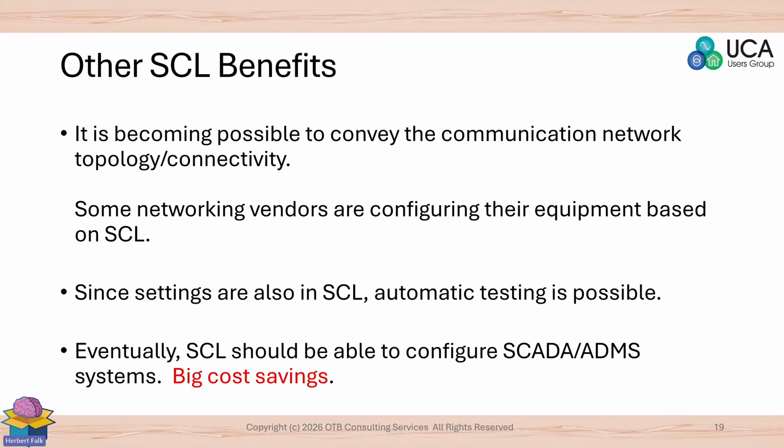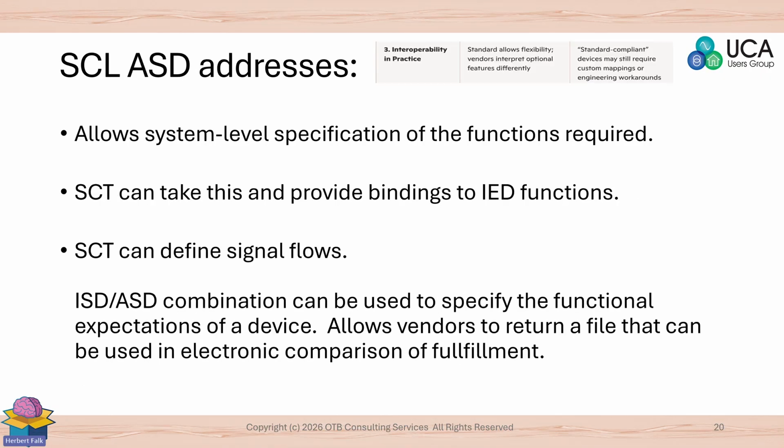Since most of the settings and measurements and control are all in SCL, it's possible to automate testing. And eventually, as more SCADA, EMS, DMS, ADMS vendors support importing SCL into their systems, that represents a potential huge cost savings.